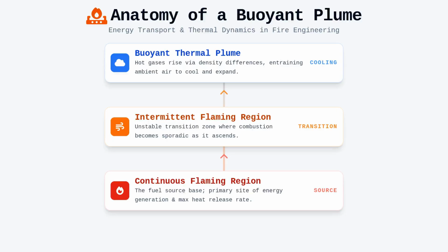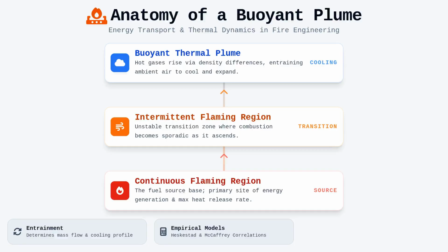Understanding these transition points is critical because the heat release rate and the geometry of the source directly influence the plume's temperature and velocity at any given height. Classical correlations developed by researchers like Heskestad and McCaffrey provide us with a systematic way to calculate these variables. By applying these empirical equations, we can reliably estimate the centerline temperature and velocity, which serve as the inputs for nearly all subsequent thermal calculations in fire protection engineering.